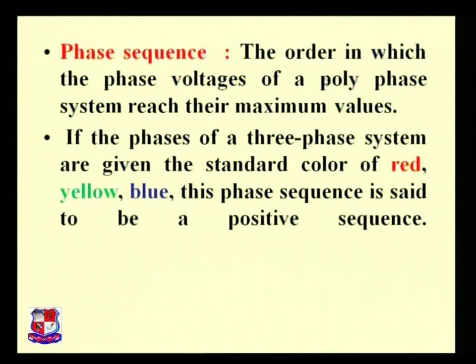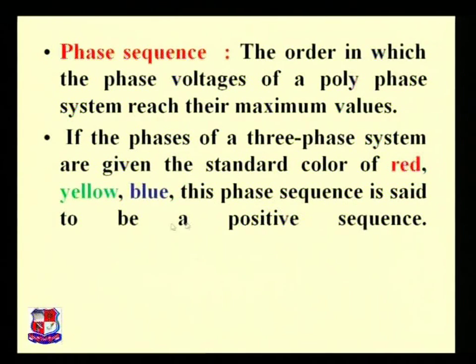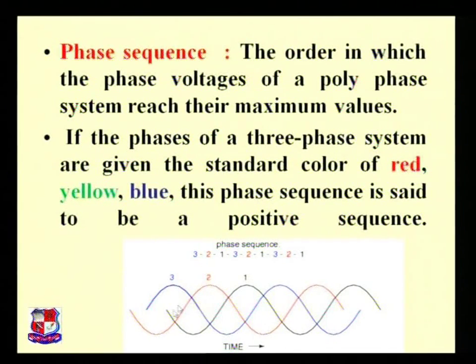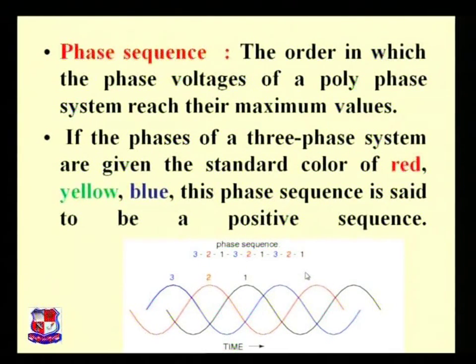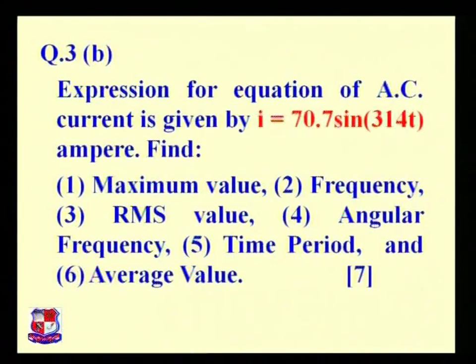Next is phase sequence — the order in which the phase voltages of a polyphase system reach their maximum value. The order is important. If the phases of a three-phase system are given in the standard colors red, yellow, blue, this phase sequence is said to be a positive sequence. In the figure, signals follow the order 3, 2, 1 repeating, which is a defined phase sequence.